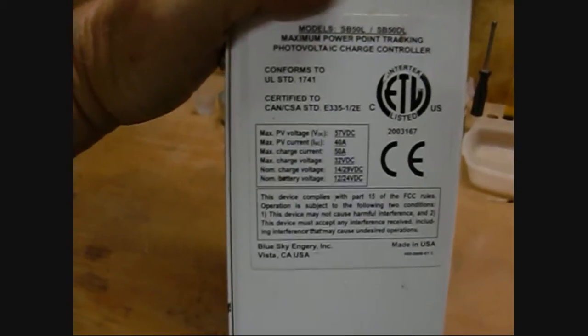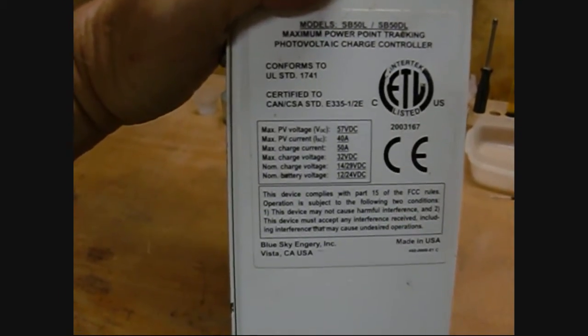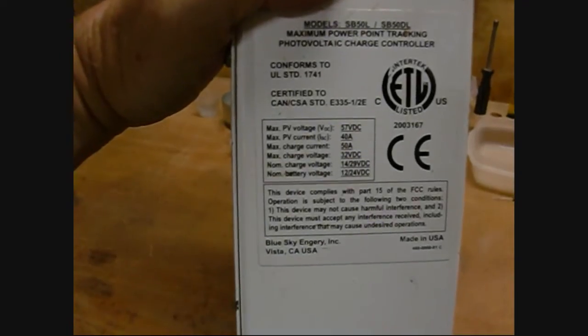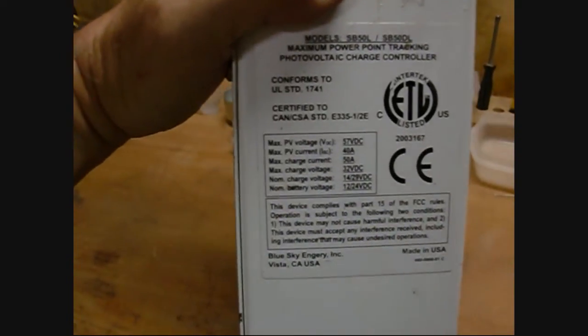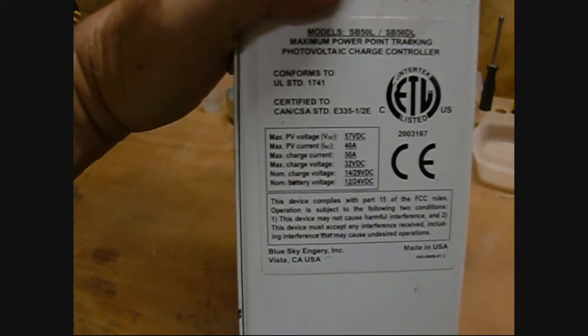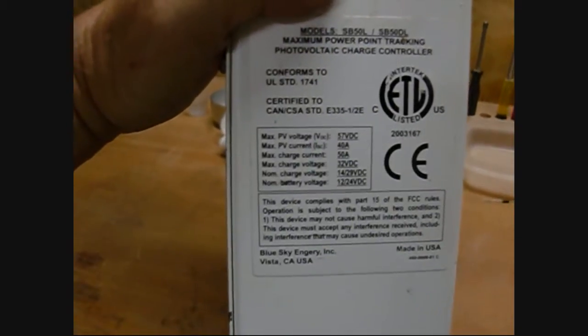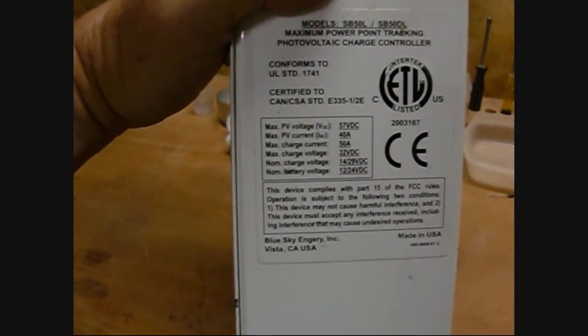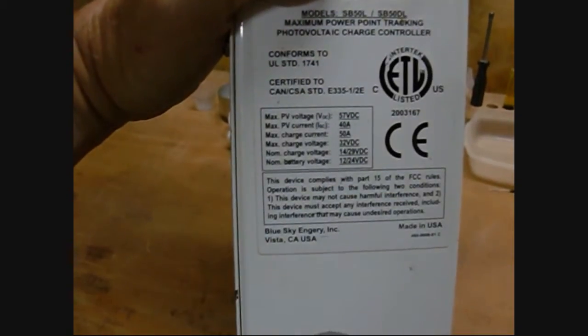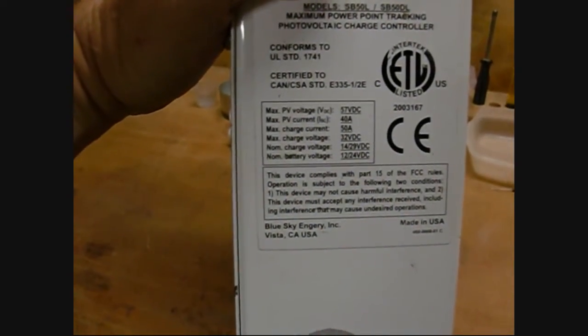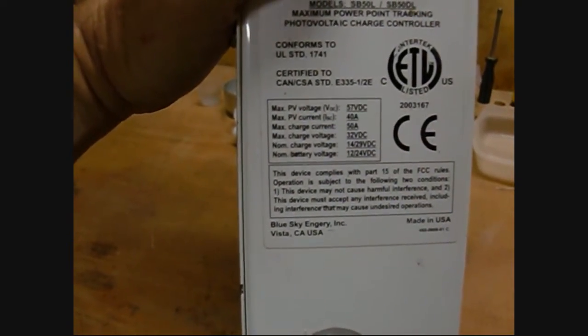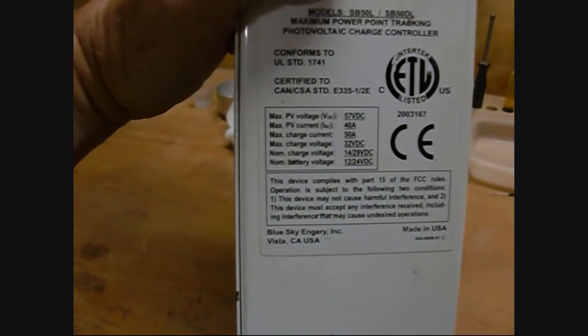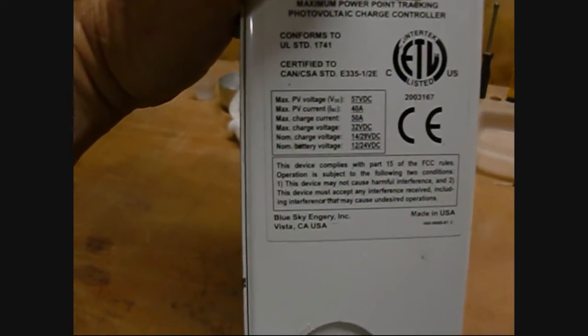...up to 57 volts input, up to 40 amps of PV power. It has a charge current output of up to 50 amps, and that's actually current limited internally, so you don't actually need a fuse, but you'll probably still need to put one on the outside breaker.